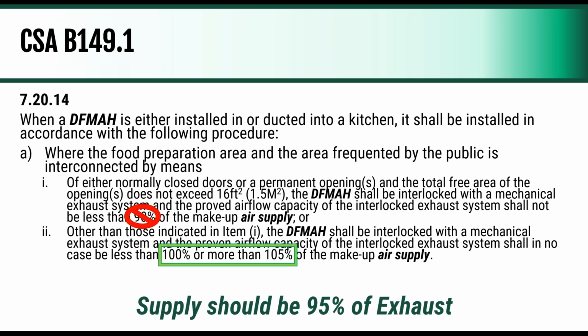The other thing that they're talking about, so basically if that kitchen doesn't have open area for air to come through, the direct fired makeup air unit needs to be no less than 100% and no more than 105% of the supply air. So 100% is neutrally balanced. 105% will be a negatively balanced kitchen because you're exhausting more than you're supplying. And that's really where we're looking at in terms of, if you want to use one number, what we typically say is size that makeup air at 95% of exhaust. That's going to meet all your codes. It's going to give you a negative kitchen, but it's not going to give you too negative kitchen.